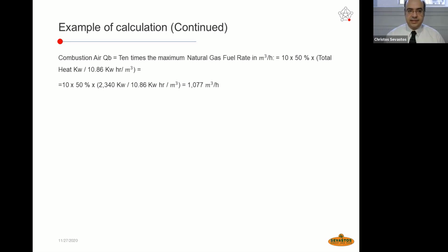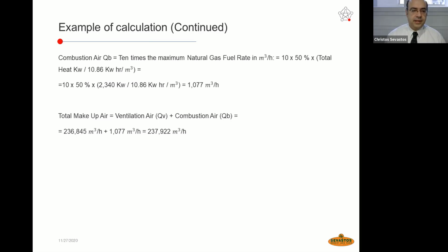As we have been discussing in the previous slides, the combustion air QB is 10 times the maximum natural gas fuel rate. If we would also like to define the air which should be supplied for covering the burning capacity of the ovens, this is 10 times the stoichiometric proportion of burning of the air. And this calculation is equal to 1,077 cubic meter per hour. The 2,340 is the total rated capacity of the oven, and this is the heat rate of natural gas. And this gives us this amount. So the total makeup air is the sum of ventilation air QV plus the combustion air QB. And this would be 238, let's say, thousand cubic meter per hour.